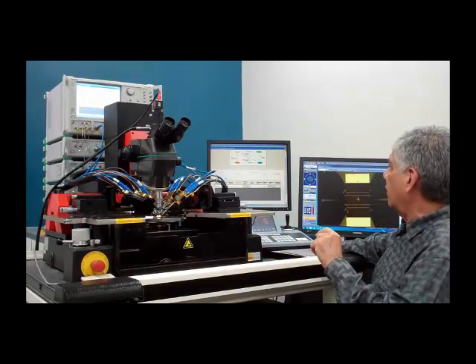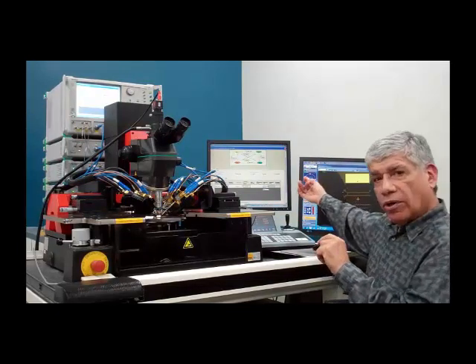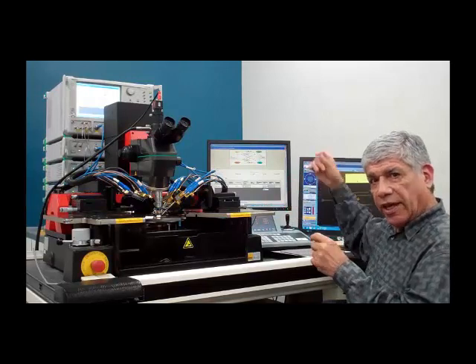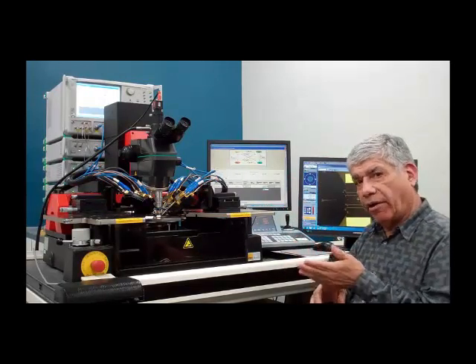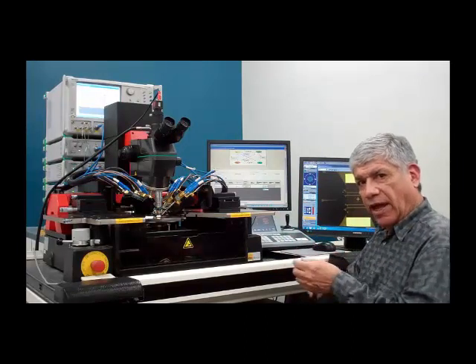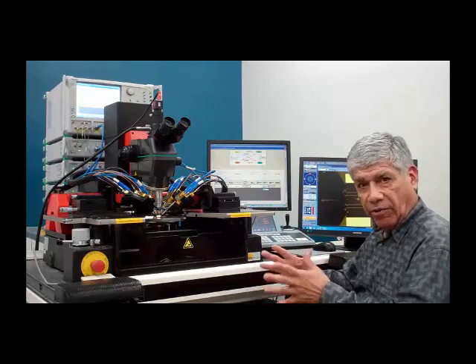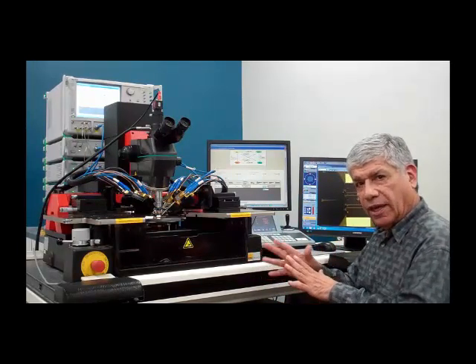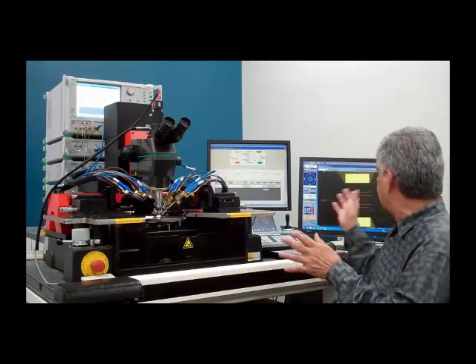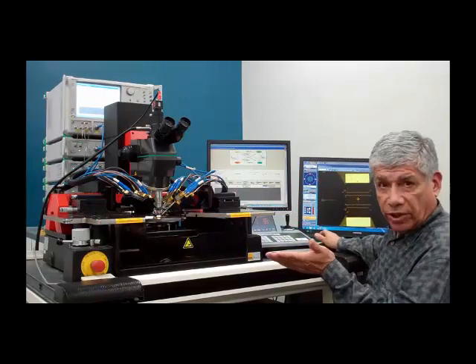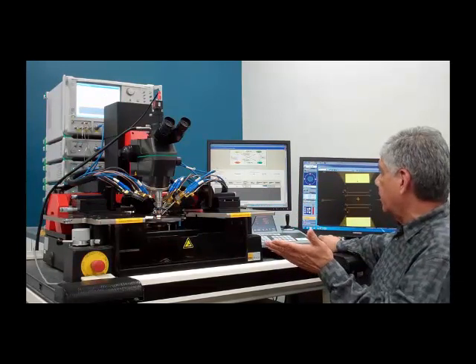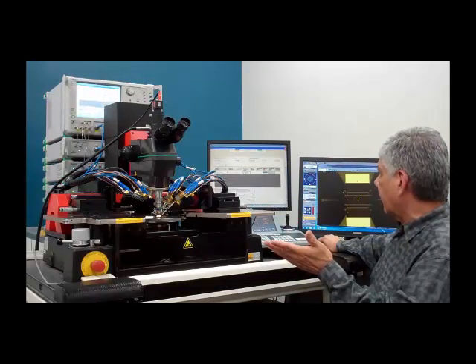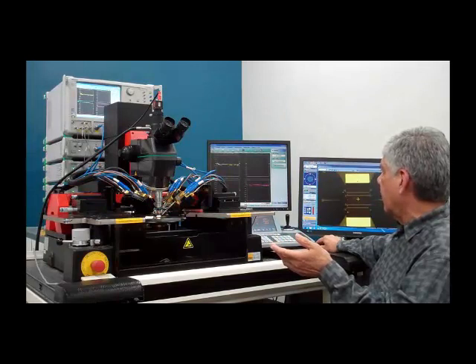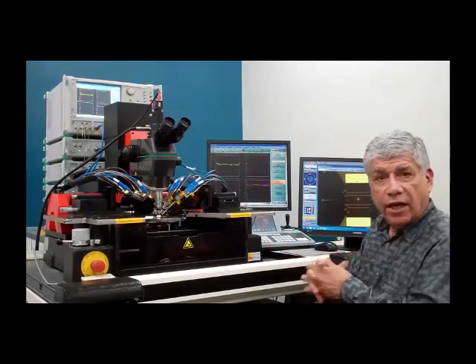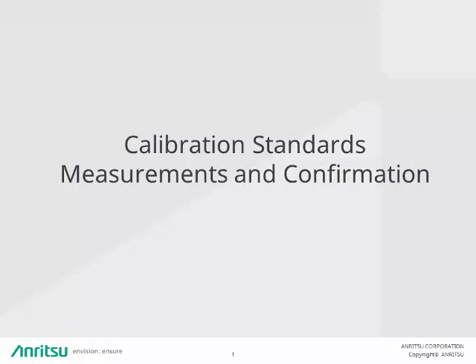And then finally, we define the reflection type, whether it's an open or a short, or it could be both. In the case of both, that's what we would call ALRM, Advanced LRM Method. And that just gives you more correction algorithms that will give you a little bit of improvement in your calibration method. For this case and for this demo, we'll just select the short only. Okay, so that's basically it for setting up for the calibration. And we exit that and then go back to our calibration menu structure so that we can set up for the different cal standards and do that measurement next.